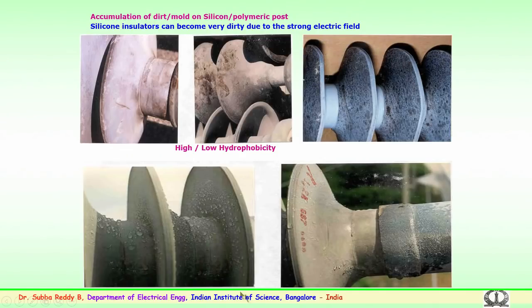There are several more failures which were reported earlier. It could be because of hydrophobicity loss, accumulation of dust, dirt, or mold over a period of time. Similarly, there is loss of hydrophobicity and the sheds being mechanically weaker. This again shows the hydrophilic nature, where water droplets start accumulating over the surface. These types of failures were noticed in the earlier stages.